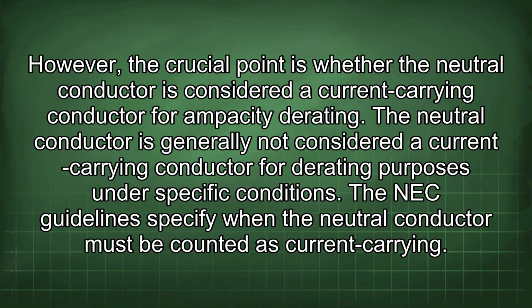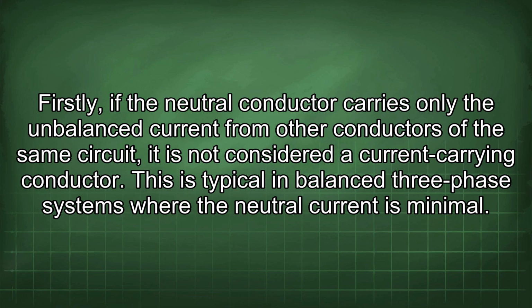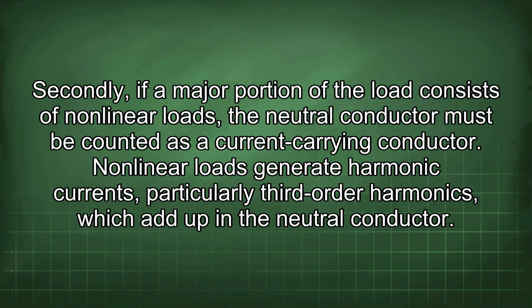The NEC guidelines specify when the neutral conductor must be counted as current carrying. Firstly, if the neutral conductor carries only the unbalanced current from other conductors of the same circuit, it is not considered a current carrying conductor. This is typical in balanced three-phase systems where the neutral current is minimal.